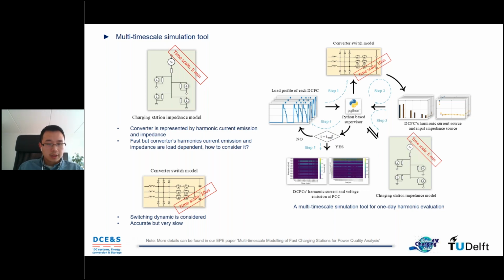How do you solve it? Well, you may use the converter switch model, then load this converter switch model with the charging profile. The impedance and current source you get from this model will be much more accurate. But you cannot use this model for, let's say, a 1 day harmonic evaluation, because it's super slow due to the very short time step.